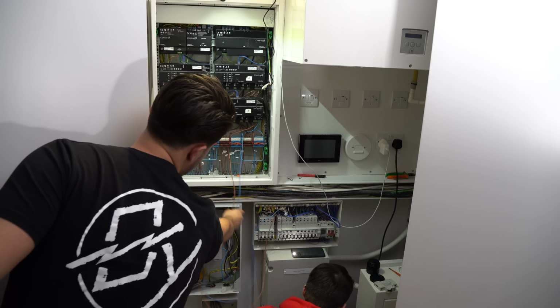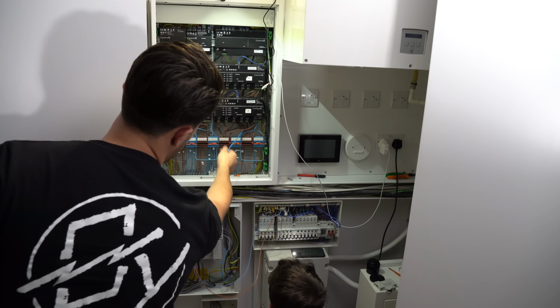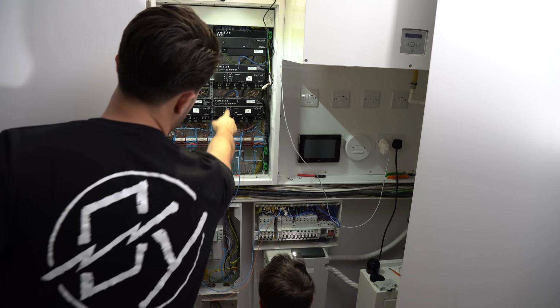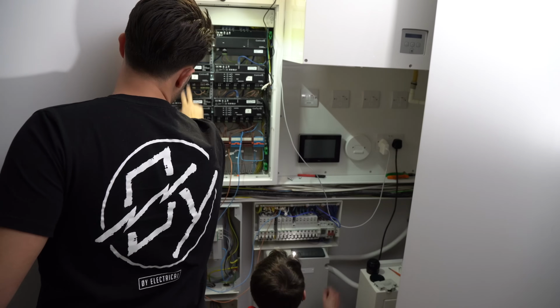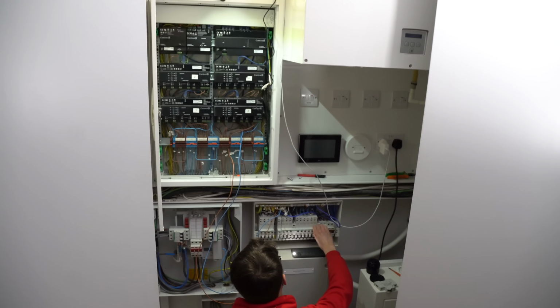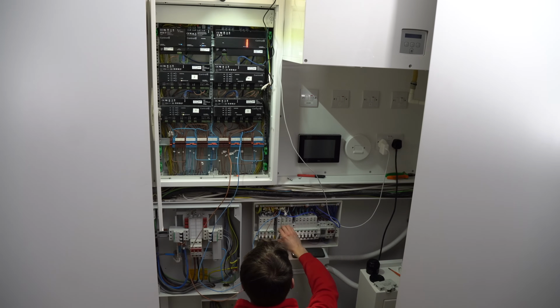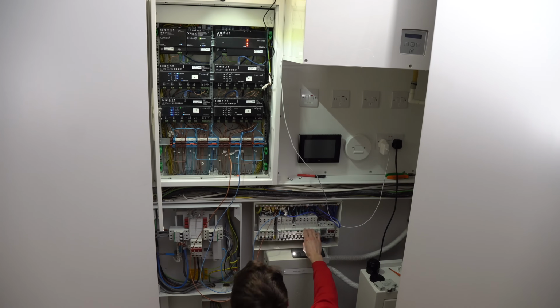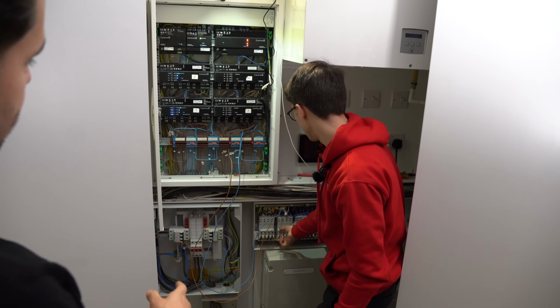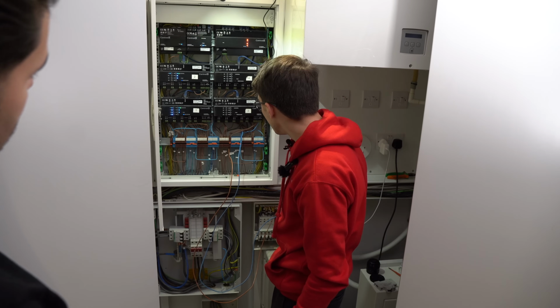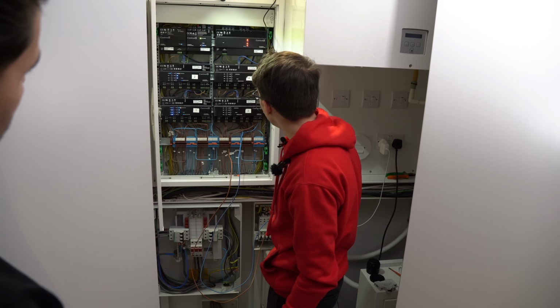So the circuit's split off. We've got this jerry-rigged in, just a temporary thing, just to see what comes live, because we're trying to split off these two dimmers from these ones here. So right, let's see what trips. Some real sight testing here. Oh, that's a good start. So those three have come live, but it's more of the shared neutrals I'm worried about. That looks fine to me. Do it.